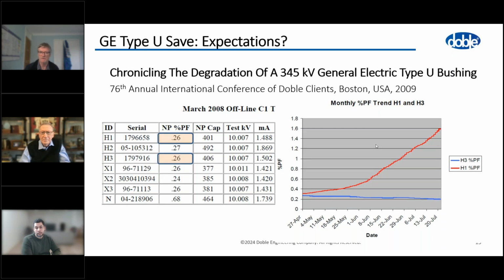So this is just one of those cases, and you can see on the left the initial 0.26. Yeah, we're not too far from that to start with, but that H1 bushing has risen a lot. We didn't have a lot of context data on this one. There was very little given to us in terms of temperature. There was no PD. It was just a case of, we've got a bushing, we need to monitor it.